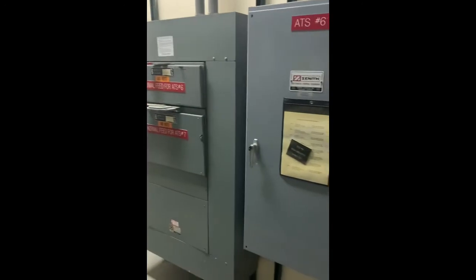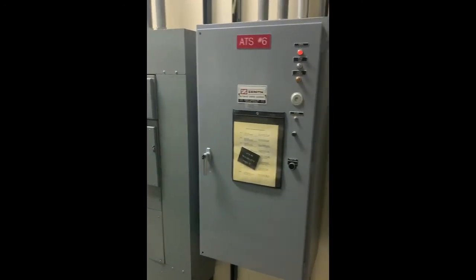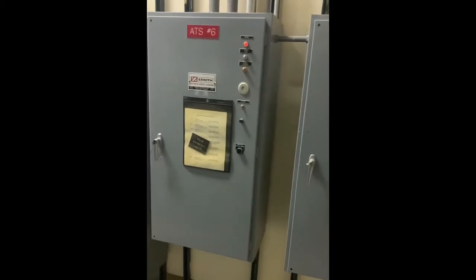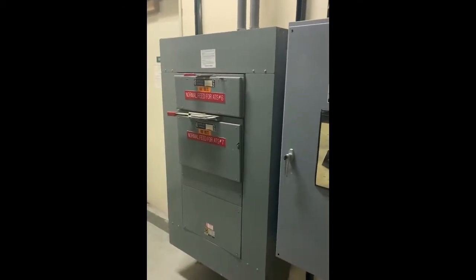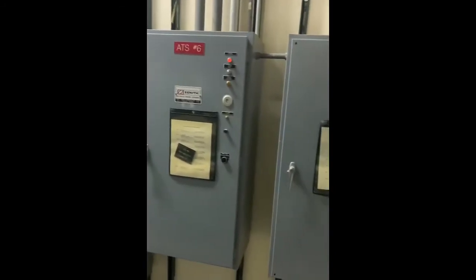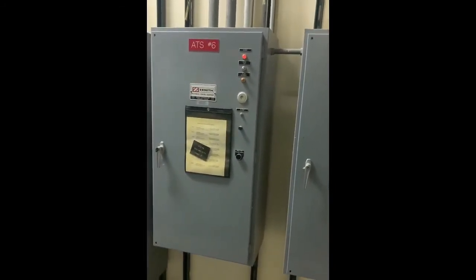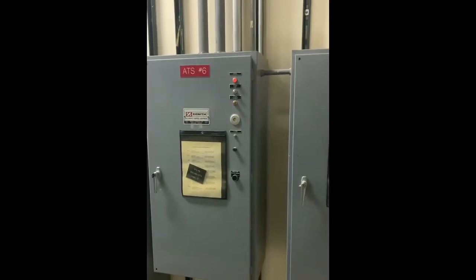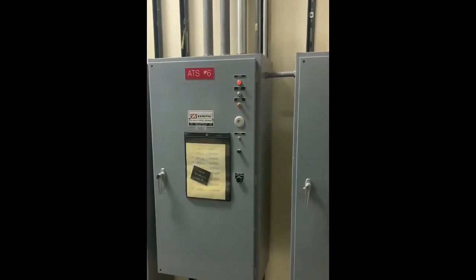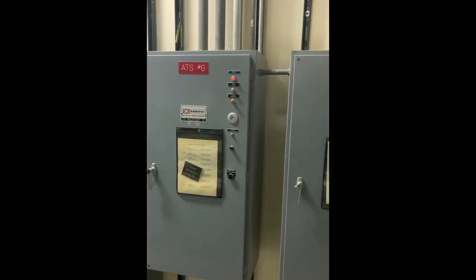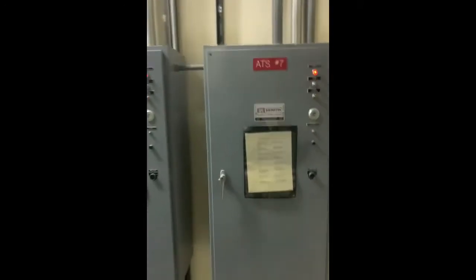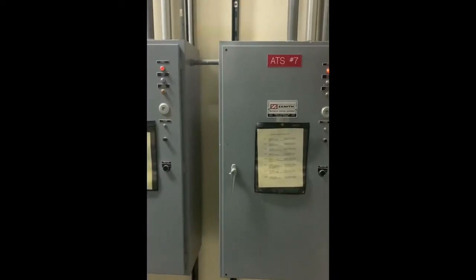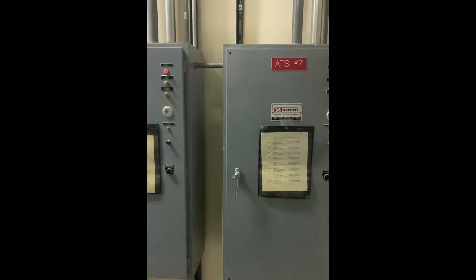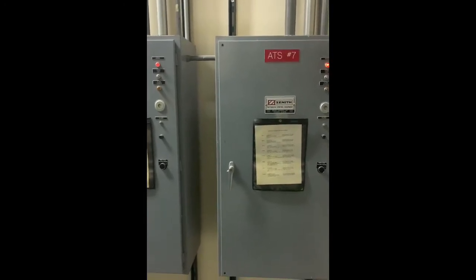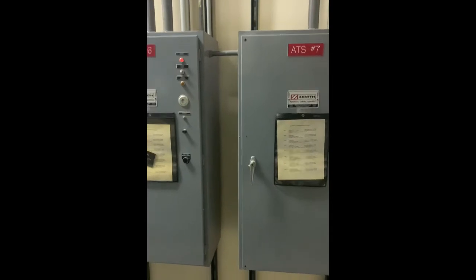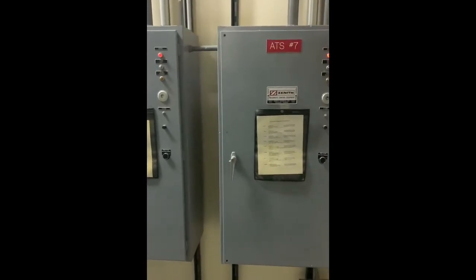Basically what these transfer switches do is monitor the power coming through the normal feed. In the event of a power failure, these switches will send a start signal to that generator we were just looking at. The generator would then ramp up the speed and take on the loads that these switches are connected to. These switches also have the ability to transfer those loads to the generator once that generator is up and fully operating.